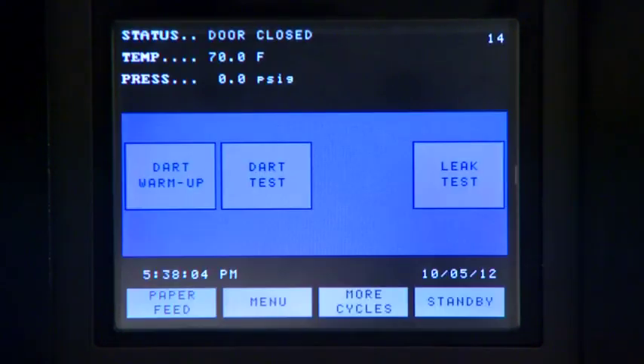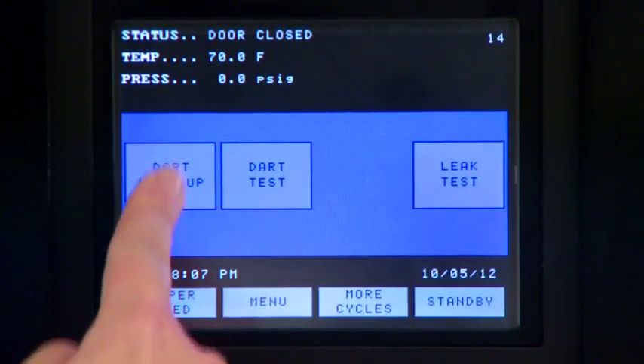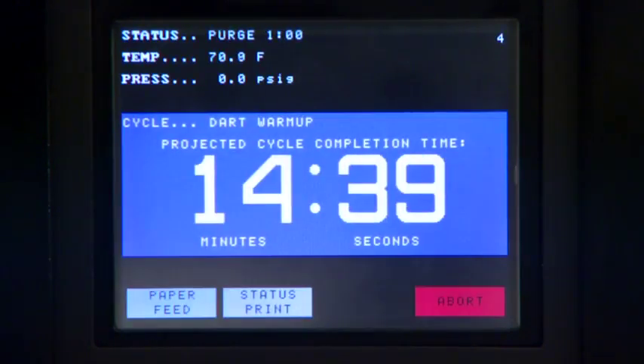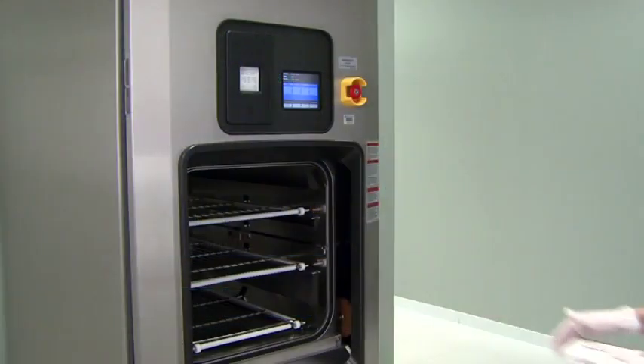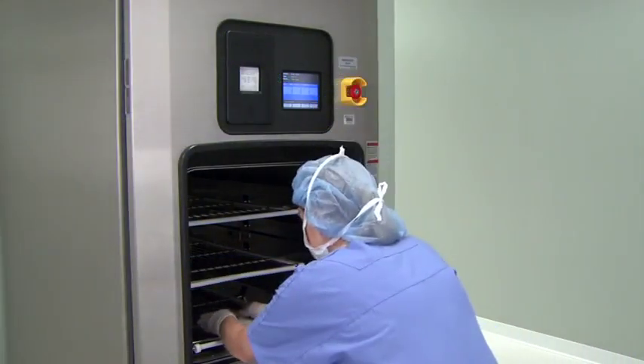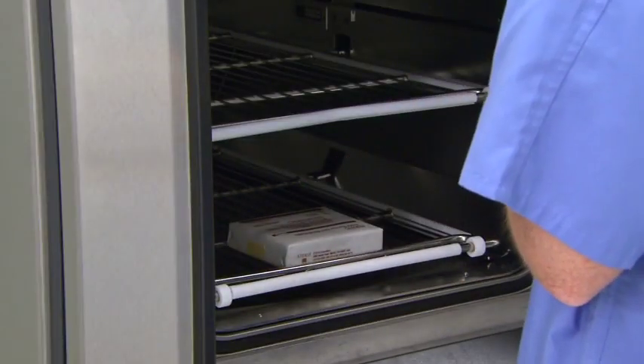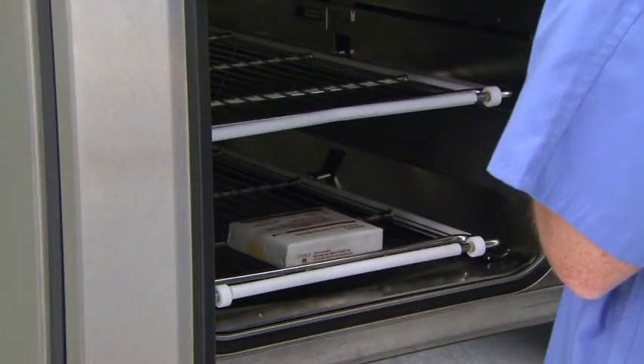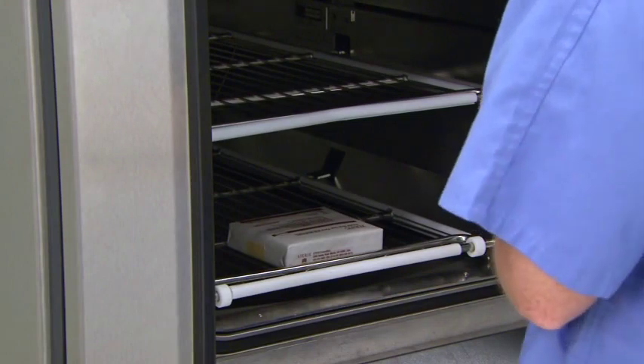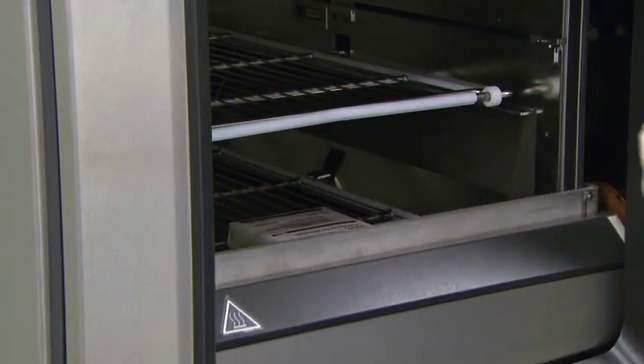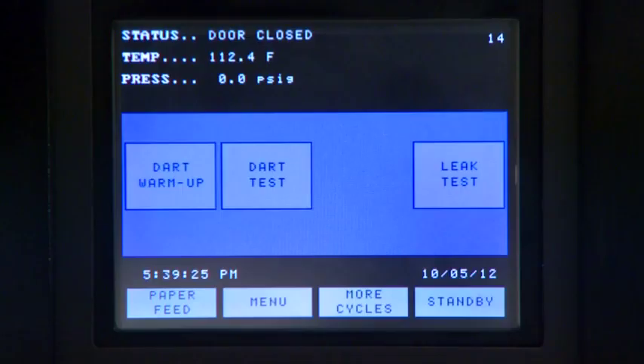To initiate a warm-up cycle, press More Cycles until the Test Cycle screen appears. Press the Warm-up Cycle button. Once the warm-up cycle is finished, place a Dart test or properly prepared Bowie-Dick test pack or commercially available test pack on the lowest rack of the sterilizer. Make sure the test pack is positioned above the chamber drain. Press the Dart test button to begin the cycle.